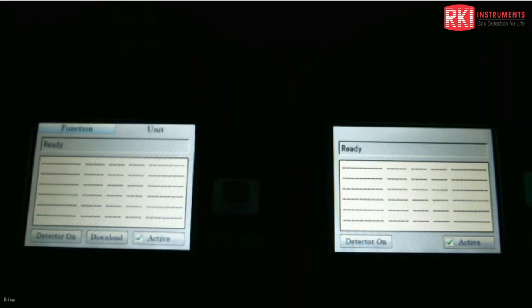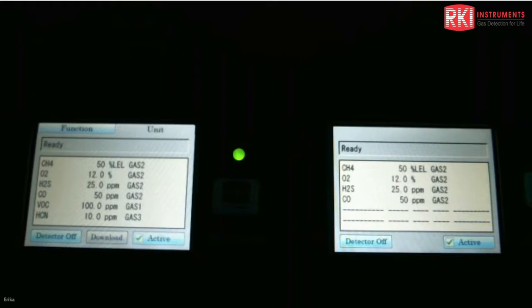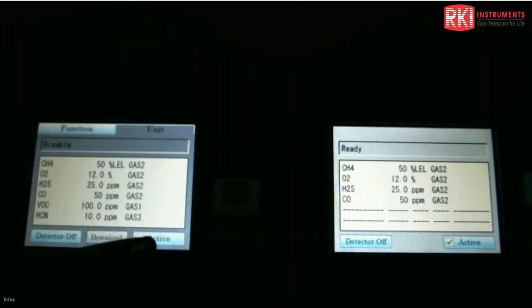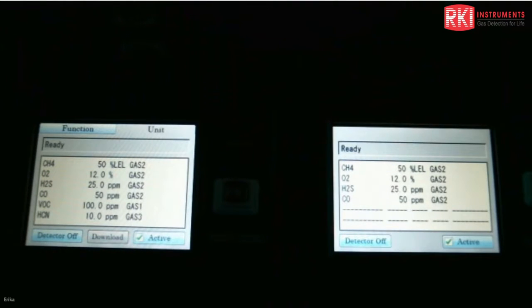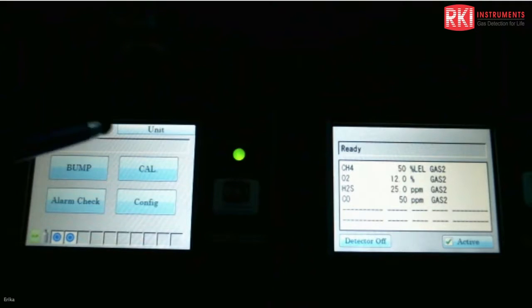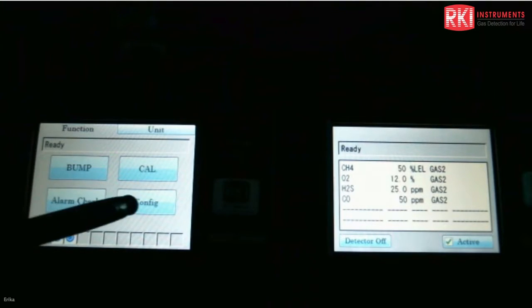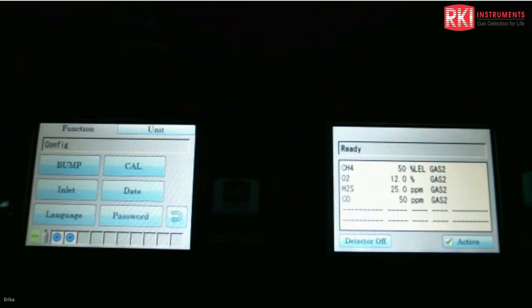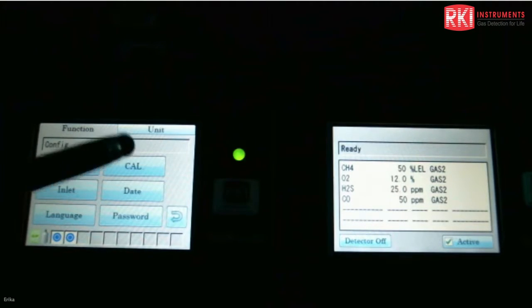So right now I just pushed in the gas in, gas out outlet just to show you that the active button can be turned on and off right there. So you can just click those, and it will pretty much disable that station. So I'm going to go back to the function tab. So here's where you can do the bump, cal, alarm check, and configuration. We'll go through the configuration first, and that's where you can adjust the bump test parameter, cal parameter. Inlet is where you can set up your gas cylinders. The date you can also set up, language, and password.